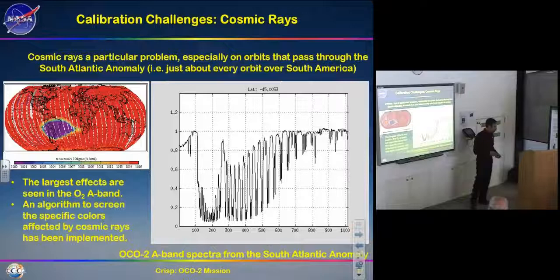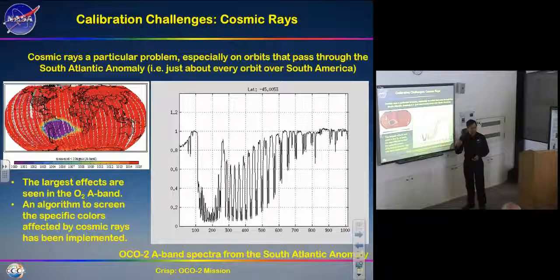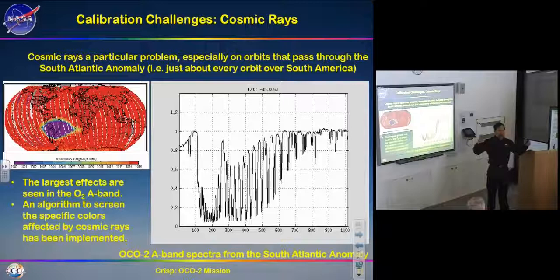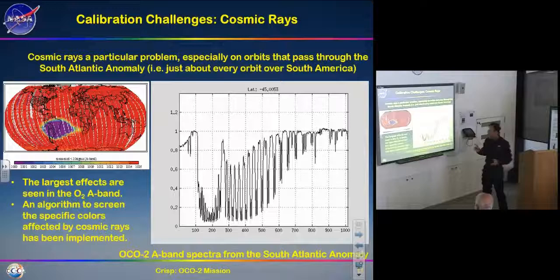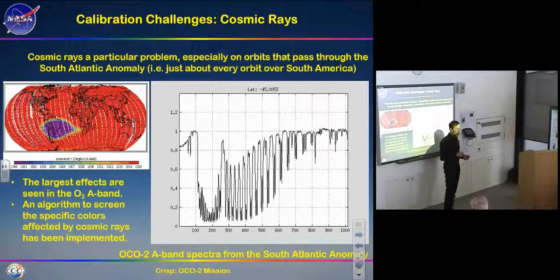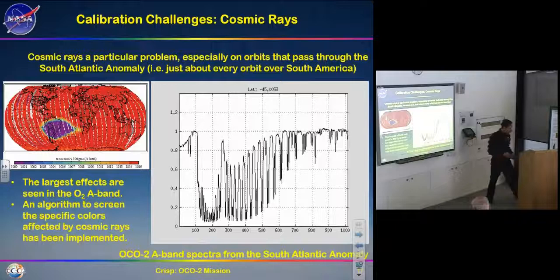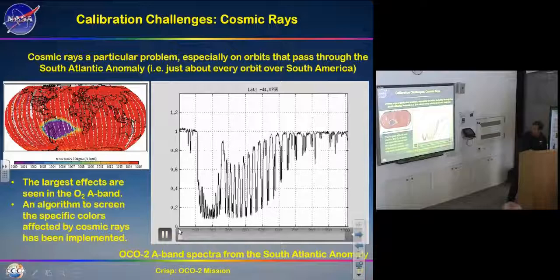In addition to expected calibration issues, there's the South Atlantic Anomaly — a region over South America where the Van Allen Belts are pulled closer to Earth by the magnetic field. We pass through this region on about one in every six orbits. When high-energy particles hit the instrument, they produce ion trails in the detectors that are indistinguishable from photons, creating a very noisy spectrum that looks like grass growing out of the top of our spectral measurements.